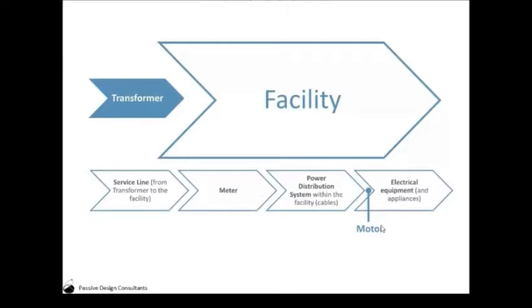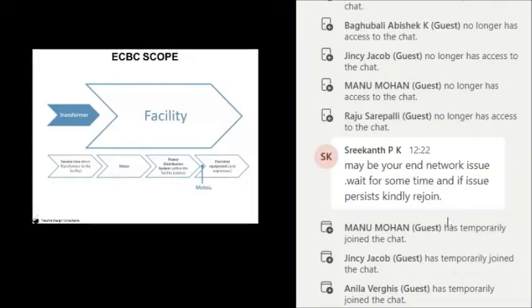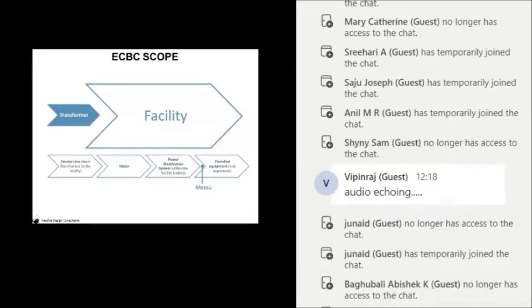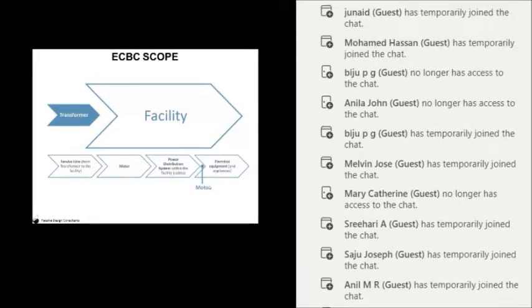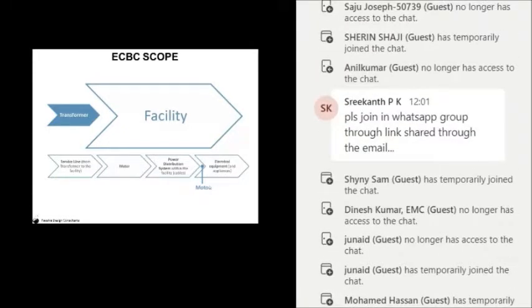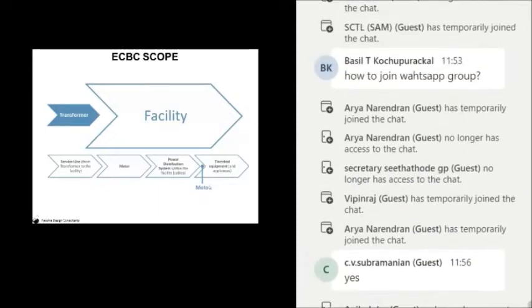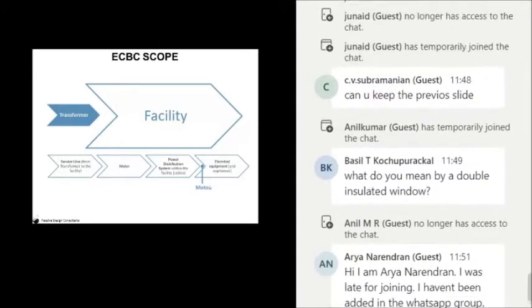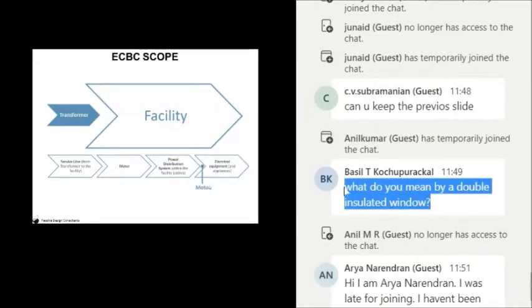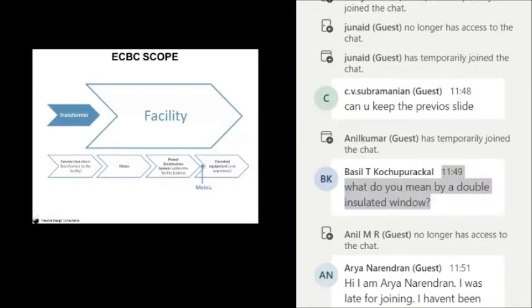Starting with the transformers, they are used to change the voltage from HT to LT, from high tension to low tension, from high voltage to low voltage in a project. Therefore, the transformers lead to a lot of inefficiency. However, these energy losses through the transformer should be minimized by using rated transformers in the project. These transformers have to be rated both at full load as well as part load, because the building does not always run at its full load.